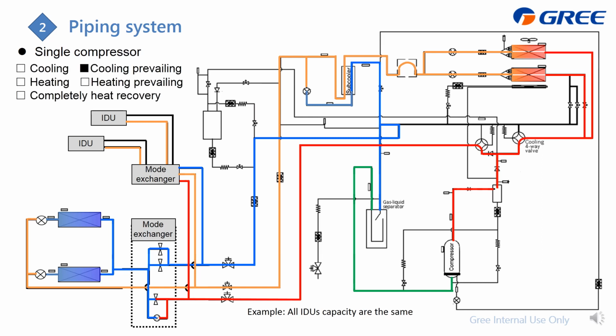For a heat pump system, there are only cooling or heating, but for a heat recovery system, there are these 5 modes. Besides the basic cooling and heating, we have the cooling prevailing mode and heating prevailing mode, and also the completely heat recovery mode. These other 3 are actually heat recovery, just with the operating mode a little bit different.